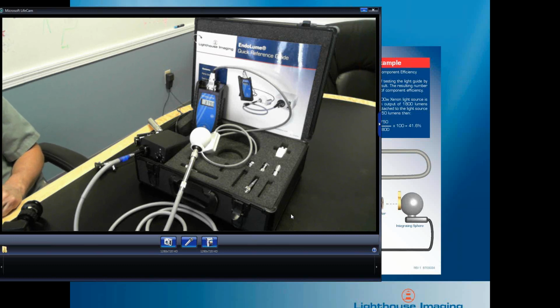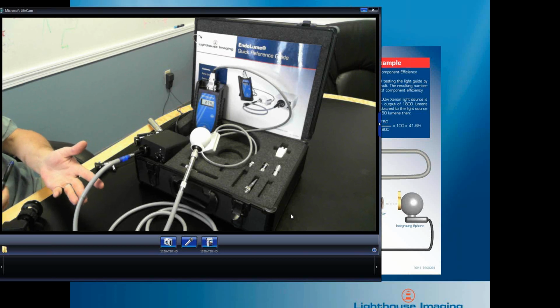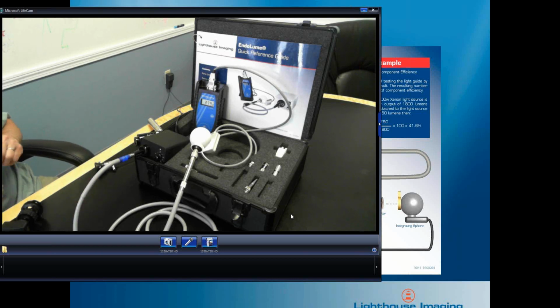I'm going to do the calculation on that. We get 380 divided by 840, 45%. So that's actually a very good output from this light cable. If we remember back to the graphic that I showed before, this is a 5mm light cable. We would expect a minimum of about 35% transmission efficiency through this type of light cable, and we're getting 45%. So this is a very good quality light cable. It's in good condition. It must not have very many broken fibers or any damage to the ends. This is how it appears. So that's a very straightforward measurement to make.